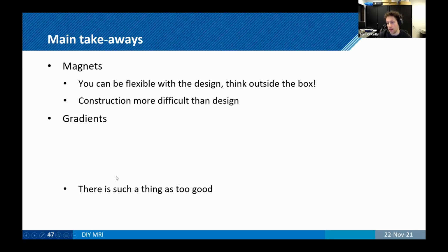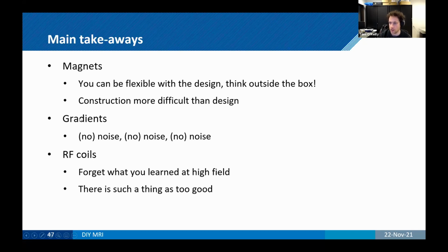For the gradients, it's kind of a no noise / noise. They're silent. You can hear a low hum when you're imaging, but just be very aware of electronic noise. This really is by far the biggest noise source inside of your system. And for the RF coils, forget everything you've learned at high field. And there is definitely such a thing as too good, just because you'll start noticing it in your bandwidth.